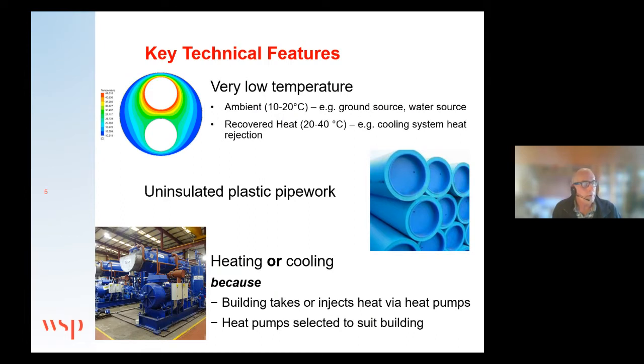If you're looking at some of the recovered heat systems with the higher flow temperatures, just to make sure you maintain the excellent performance, you may look at insulating your flow pipework, but you'd very rarely be insulating your return pipework. That's all based on the idea that these systems are buried underground. If you come above ground, you probably will be wanting to insulate.